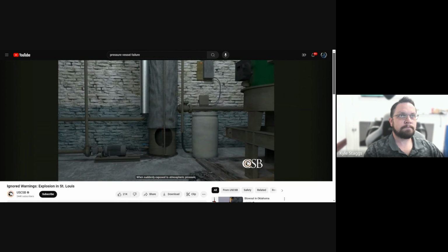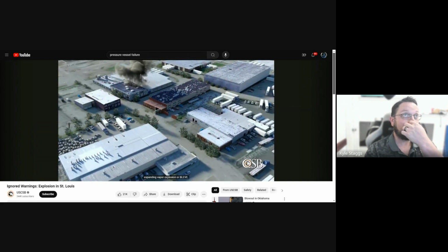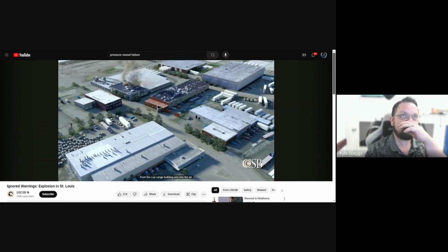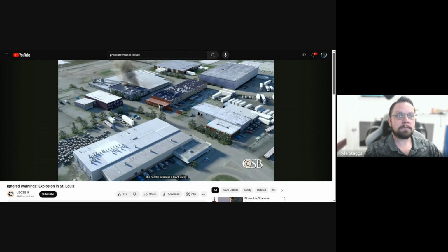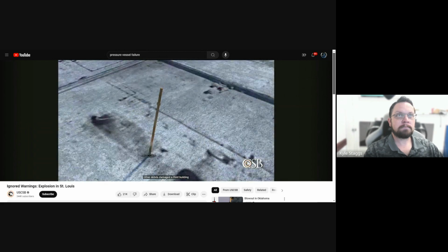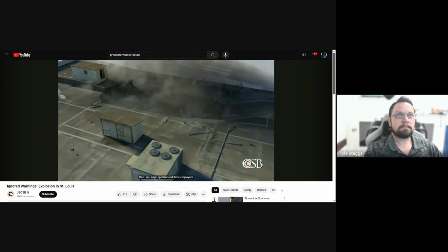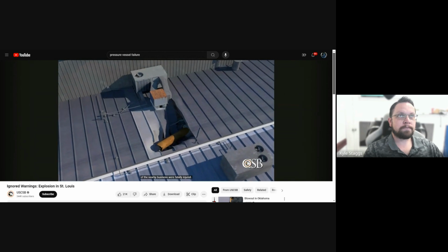When suddenly exposed to atmospheric pressure, the water in the vessel flashed into steam, greatly expanding in volume. The result was a boiling liquid expanding vapor explosion, or BLEVE. The explosion launched the SCR from the Loy-Lange building and into the air. It traveled 520 feet, crashing through the roof of a nearby business a block away. Other debris damaged a third building as well as a parked vehicle. One Loy-Lange operator and 3 employees of the nearby business were fatally injured.